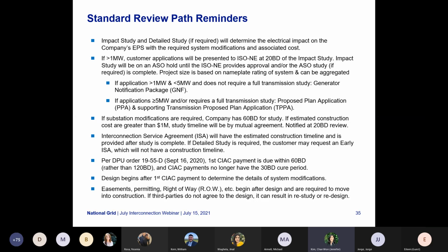If we have determined that a detailed study is required, the customer may request an early ISA. However, do note that this will not have a construction timeline and will begin your payment timeline. And then per the DPU order 1955, which came out last September, the first payment is due within 60 business days rather than the previous 120 business days. And the payments will no longer have the 30 business day cure period after the payment due date has passed. And then design begins after the first payment has been made, and this is to determine the details of the system modifications. And easements, permitting, right of way, and such will begin after design and are required to move into construction. And if third parties do not agree to the design and do not approve such easements or permitting or right of way, then it can result in a restudy or a redesign. Next slide.